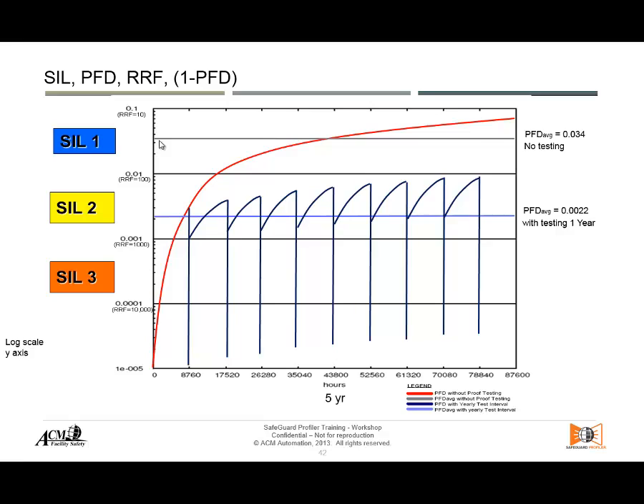Why? Because we're testing the equipment and making sure that it's working. So the probability that it's going to work when required will be much higher, or the probability of failure will be very low. That means I will have a higher SIL 2, better reliability, and my probability of failure on demand will be lower than 0.034, just by proof testing every year — including imperfect proof testing.